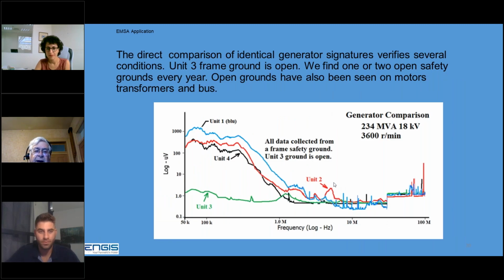Here's a safety ground open on a GE generator. This particular site has 4 identical machines. Unit 1, Unit 2, Unit 4. The signatures are almost identical. Really nothing wrong with those generators, but the safety ground on 3 is open. And we find 1 or 2 open safety grounds every year.